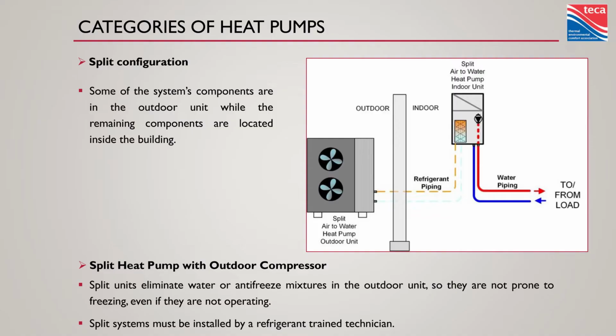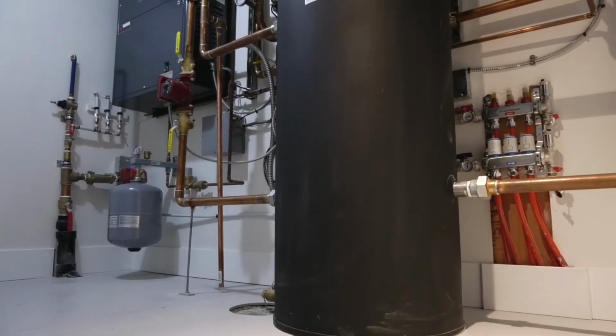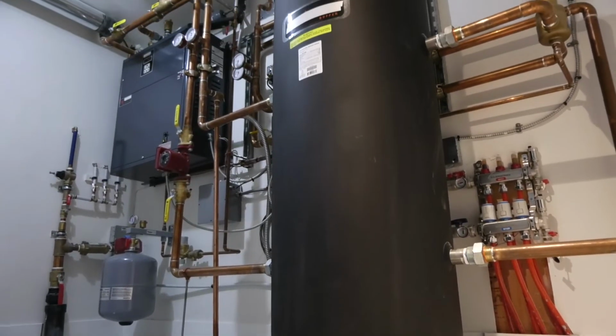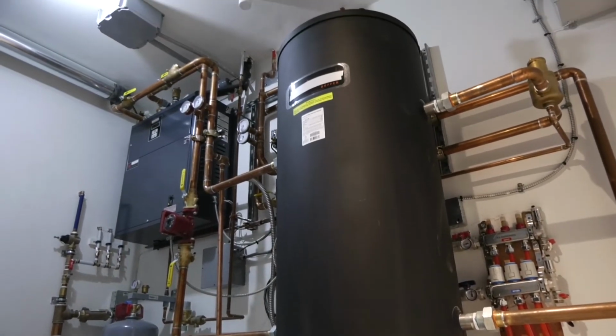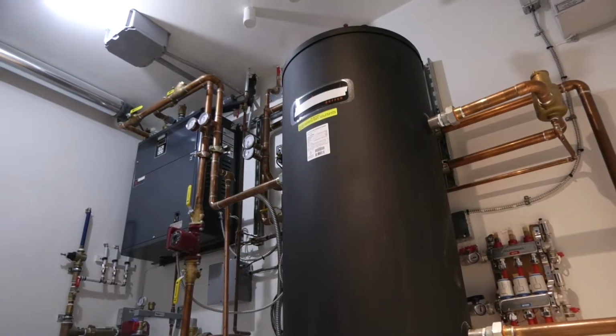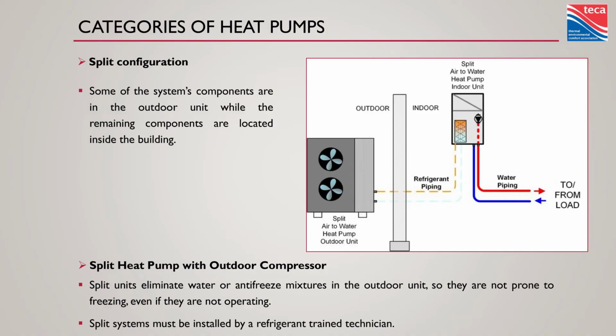So we've got water lines, refrigerant lines, maybe a condensate drain if it's running in chilled cooling. But very easy to integrate into the beautiful mechanical rooms I know you guys like to make. Nice part about this is now the water lines are not outside. Refrigerant's not going to freeze when it's cold out, so we don't have to use glycol in a system like this.